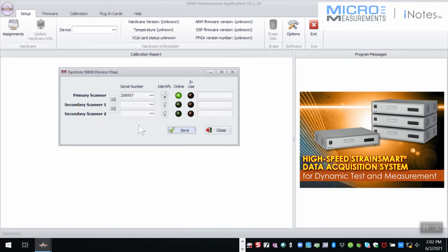Yep. And before you go, if you get to this point and you find that you're having trouble with the communication, this is the point when you need to go back and check all the things that you think are done or correct. And that could be as simple as, do you have the Ethernet cables plugged into the right location on the back of the scanner? Do you have the power turned on your router? Are you using the LAN ports on the router? Do you have your computer set up for DHCP? That's where you're going to go through and check those things and make sure that you dot all the i's, cross all the t's in order to get this thing talking. Because really, quite frankly, with DHCP, it should be easier than what you find if you have to give it a static IP address. That's the intent.